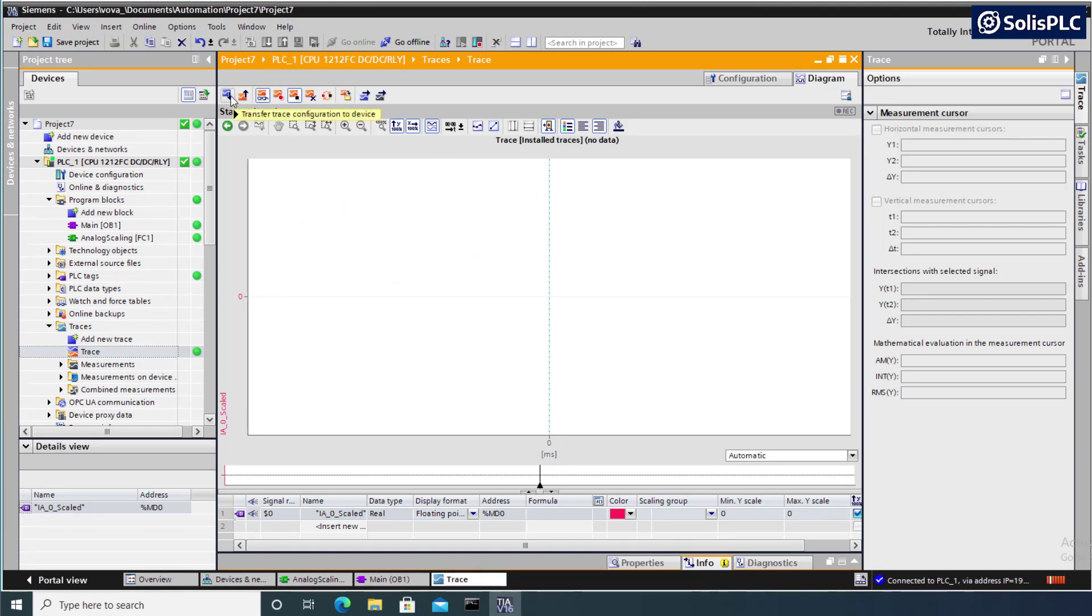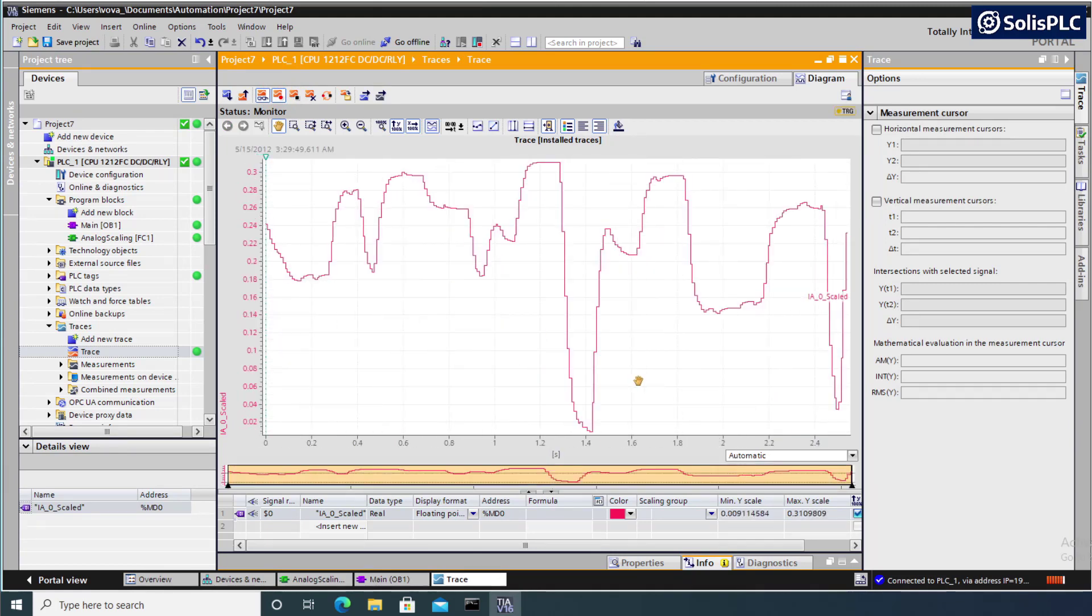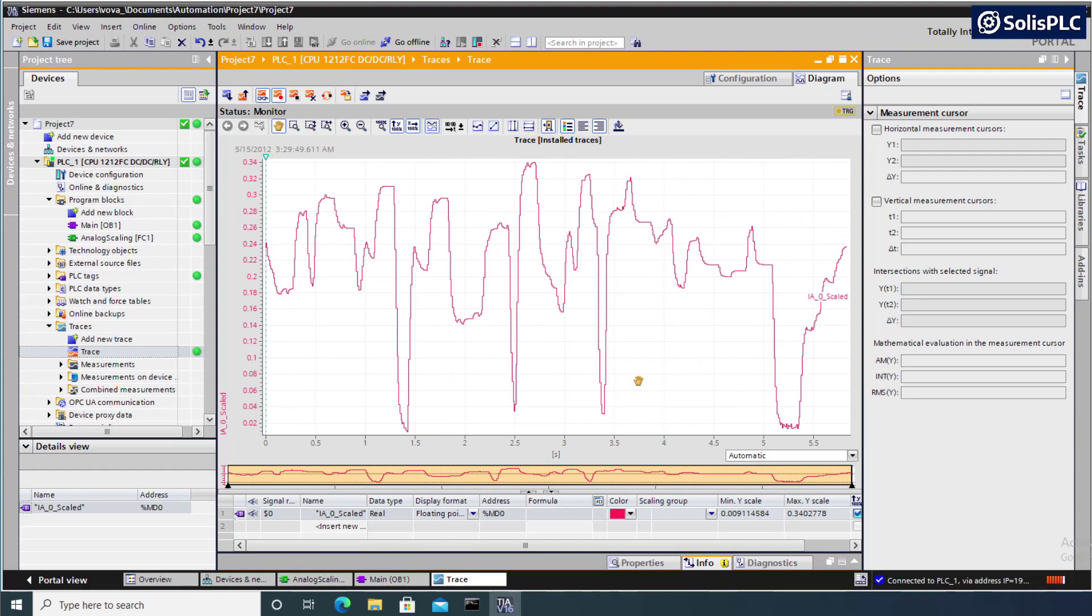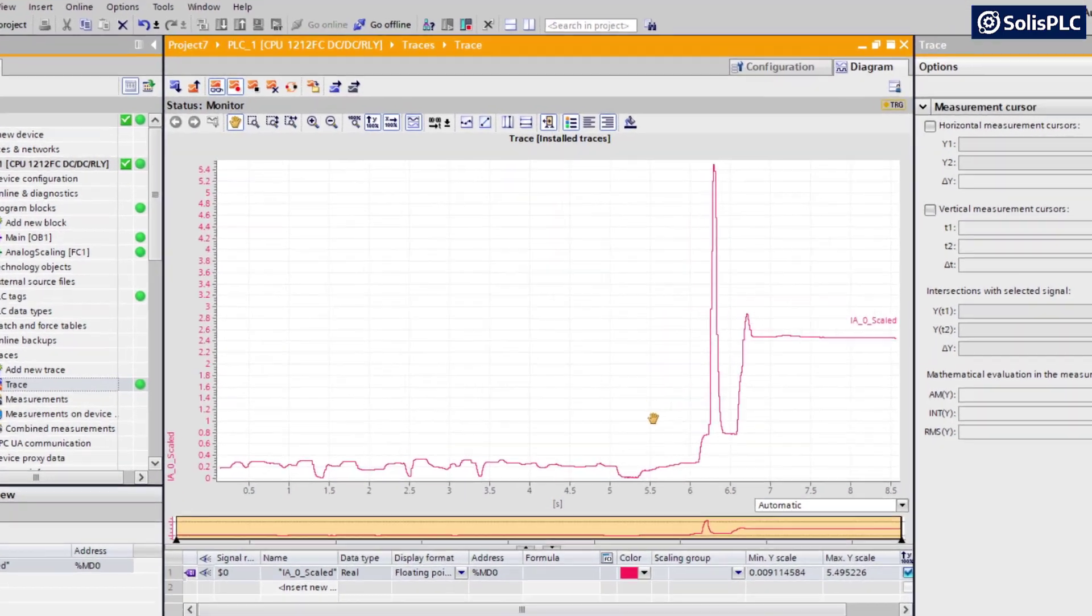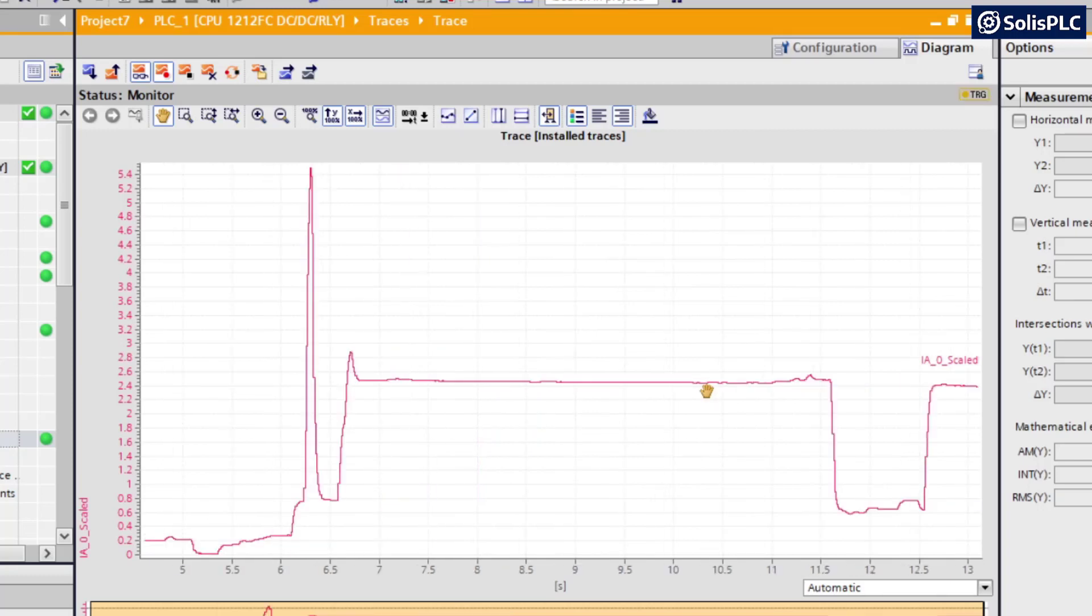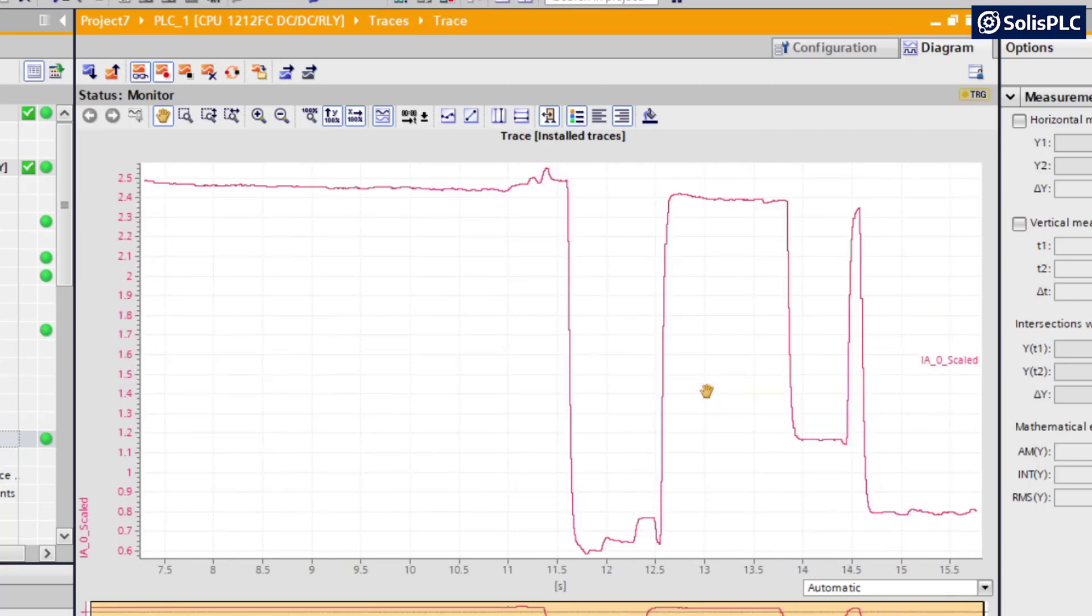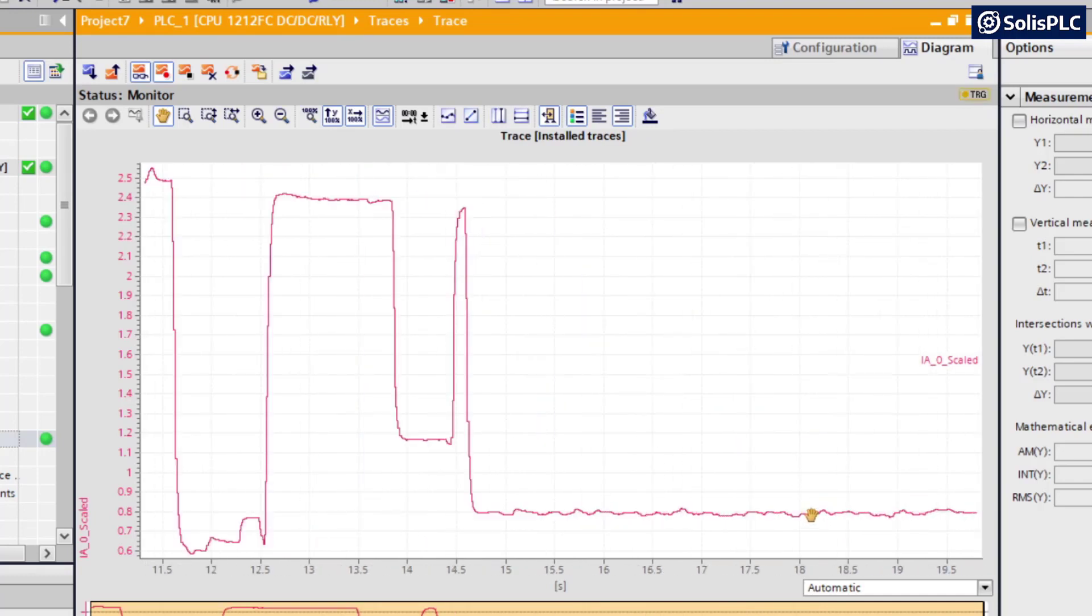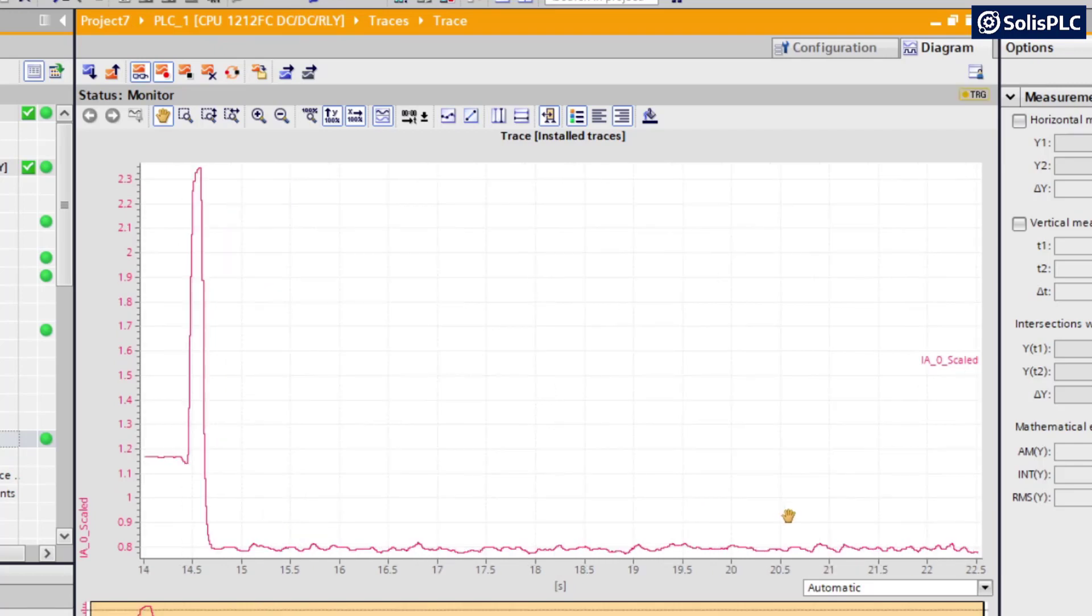Once we have the trace downloaded to the PLC, we can press on this activate recording. And we're going to get an analog signal based on the readings we get of that function. So if I point the sensor back at the wall that I've had it pointed to before, you'll notice that the reading is going to be fairly stable at that 2.6. If I point it back to the monitor, it's going to start looking at a value of 0.8, which we've also observed in our main routine.